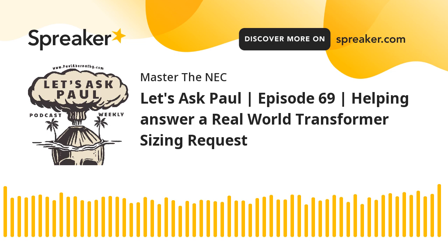And because I'm dealing with note 1, which says where the 125% of the current does not correspond to a standard size, then I can go up to the next higher standard size. So I'm going to put a 70. So I'm going to have a 70 amp. If it's a 45 kVA transformer, I have a maximum 70 amp on the primary. If it's a 30 kVA, I want to have a 45 amps on the primary.